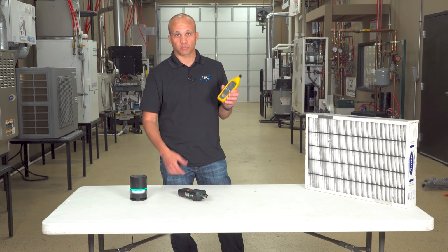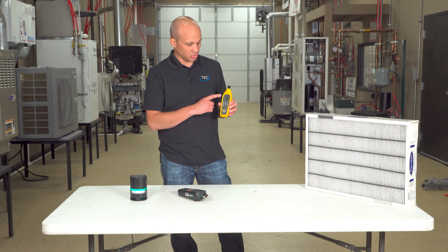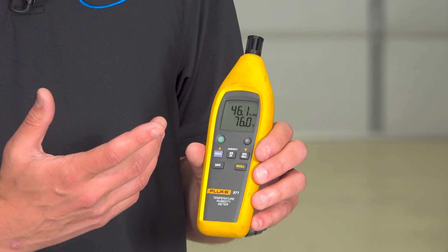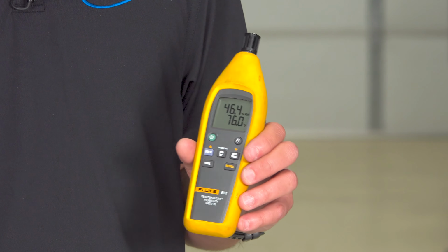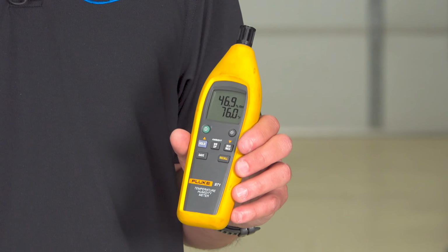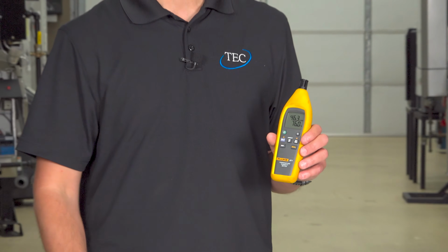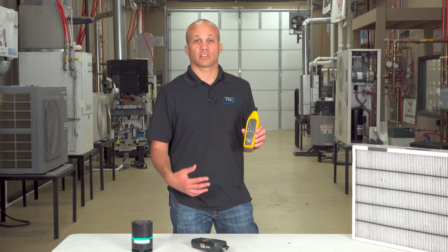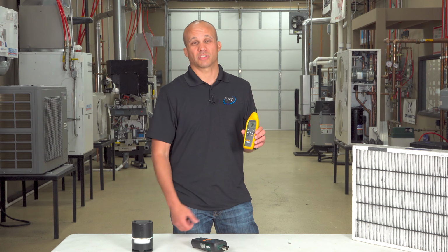So I have my handheld probe here. There's all kinds of different versions and models of these types of things. This one happens to be showing me currently percent relative humidity and temperature. So it's 76 degrees in here right now, and it's 46% humidity, which is fairly low, and that's great. When you start getting above 60%, that's when a little trigger in your head should say, hey, there could be a problem. There's a couple different ASHRAE standards that reference maximum humidity in spaces. One is for human comfort, 60% maximum. The other one's for indoor air quality, 65% maximum. So you don't want to get above 65%.